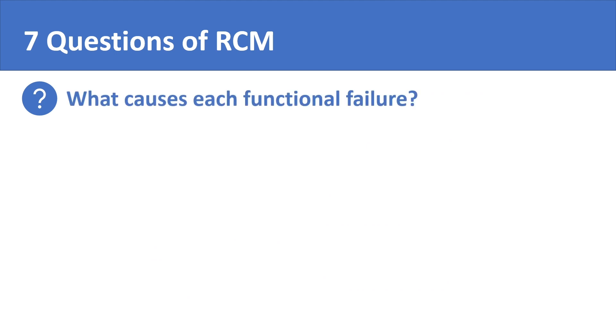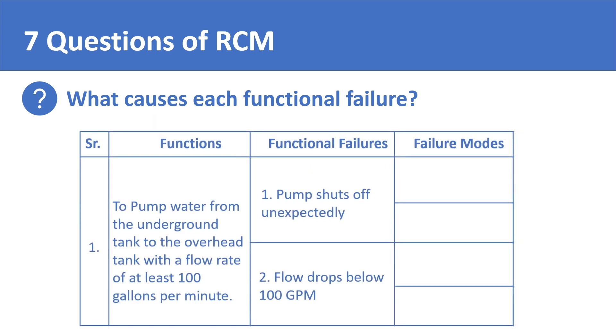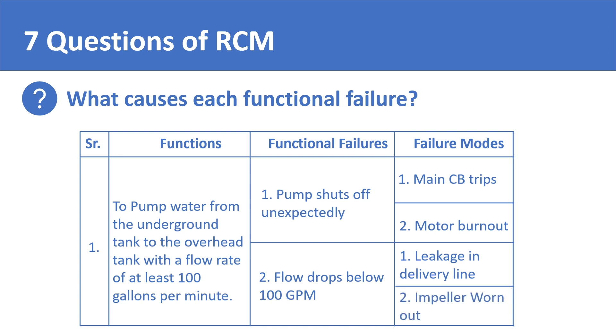The third question of RCM is: what causes each functional failure? The cause of a functional failure is called a failure mode. The pump could trip because of its circuit breaker or because of a motor burnout. The pump's flow rate could drop because of a leakage or because of component wear. The third step of RCM is about working out all the different failure modes that the equipment in your plant could experience.